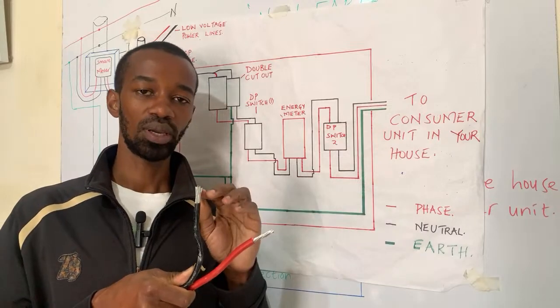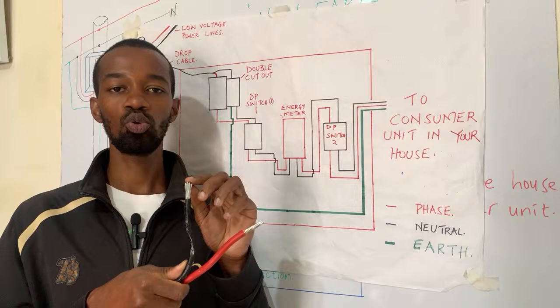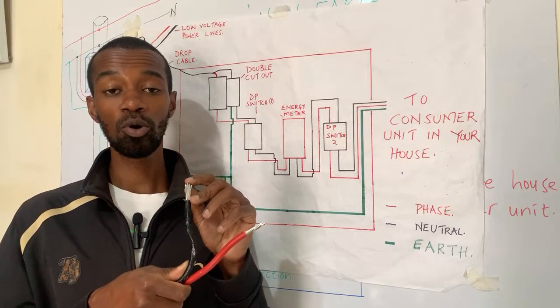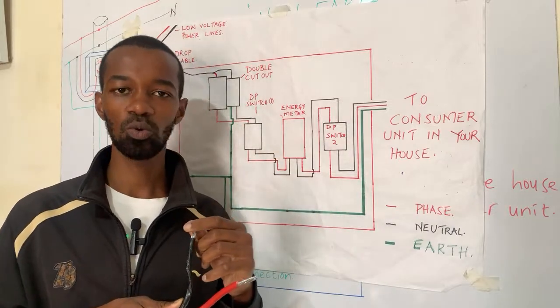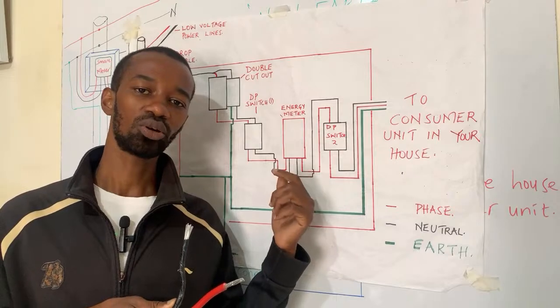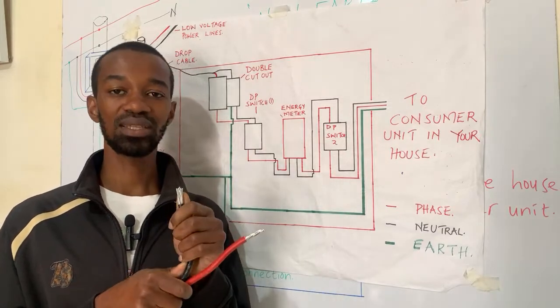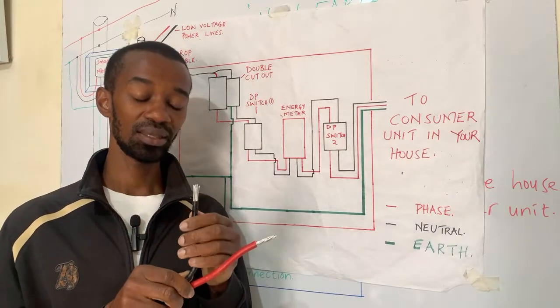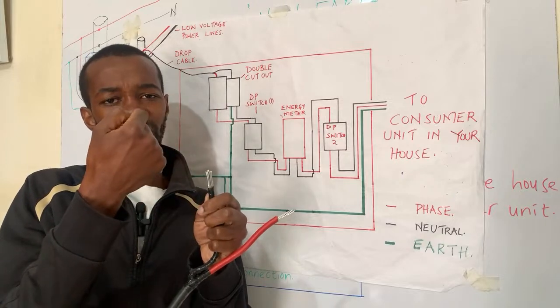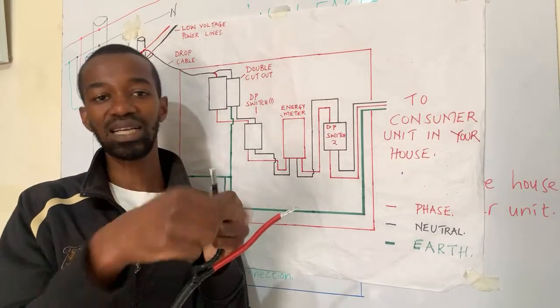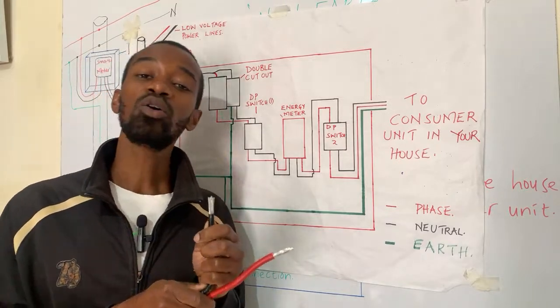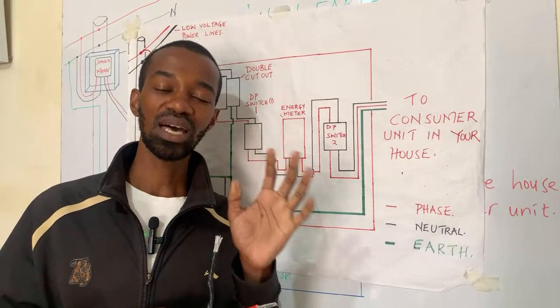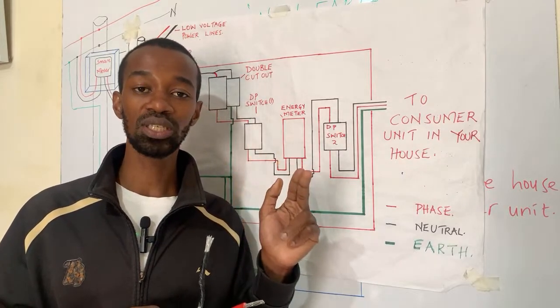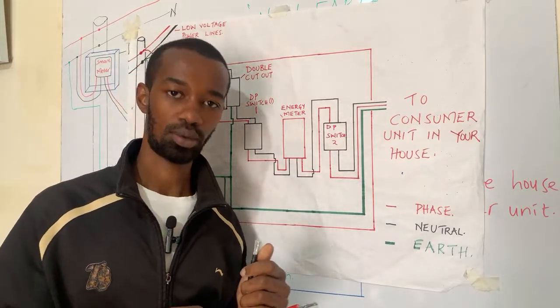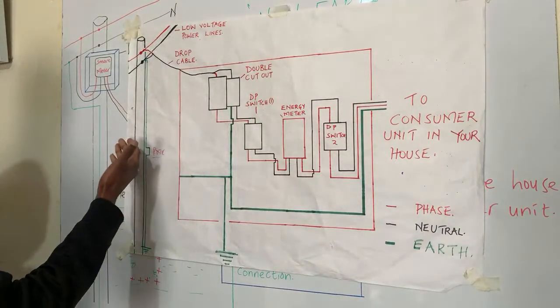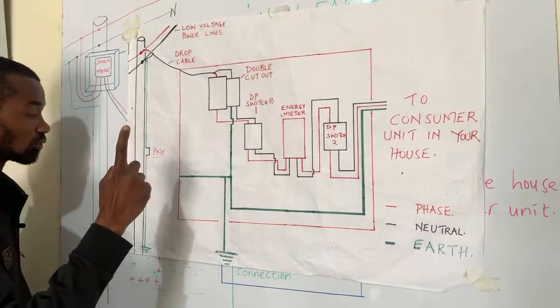And therefore there will be something we refer to as a floating neutral. Many people refer to it as just a return. This wire or connection has a return. But in actual sense, what that means is that the neutral is floating in that path, meaning it is not finding its way back to the transformer to complete that loop or circuit. Now, that return path or connection, if it is compromised, it will cause a shock. All right. Meaning it is not finding its way to the transformer. It has nothing to do with the earth connection, all right?